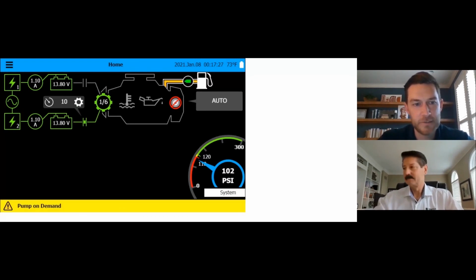The engine's cranking. Like I mentioned, you can see right now it's pulling from battery bank 2 and it's trying for 6 more seconds. And it's number 1 of 6. So if it's not successful here, it's going to take a break for 15 seconds, and then it's going to try from battery bank 1. And it will continue to do that 6 times until it eventually fails to start, which is one of the tests that you have to run when you're starting up a diesel.